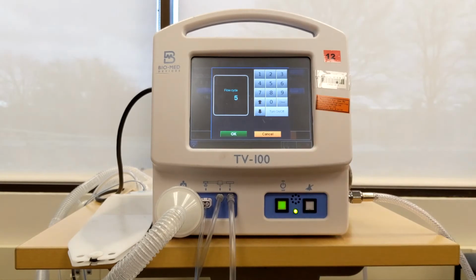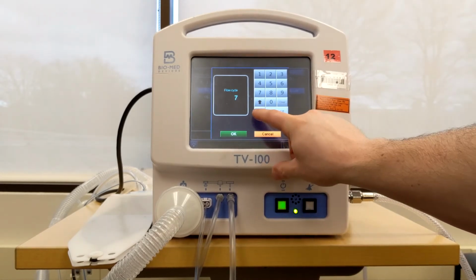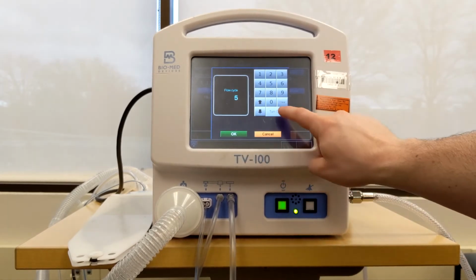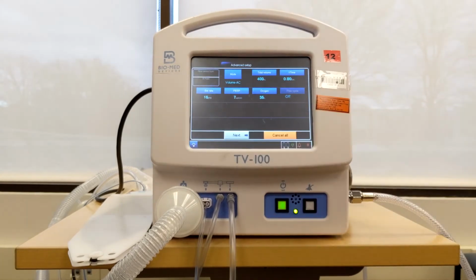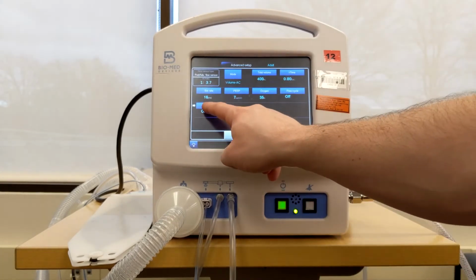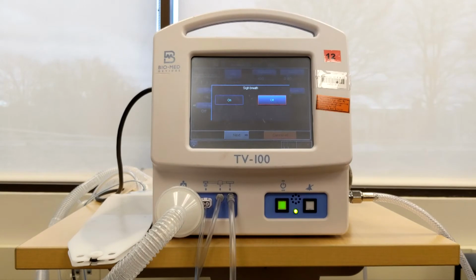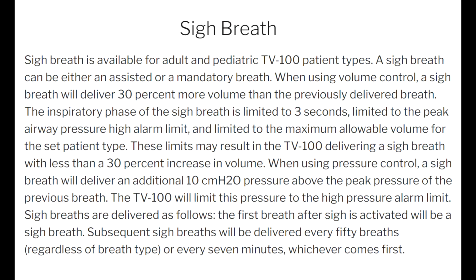Since we are using an artificial lung and will not be able to mimic flow, we will turn this setting off. The TV-100 also has a sigh breath setting. The ventilator can be programmed to deliver an occasional sigh with a larger tidal volume. This prevents collapse of the alveoli, or atelectasis, which can result from the patient constantly inspiring the same volume of gas.